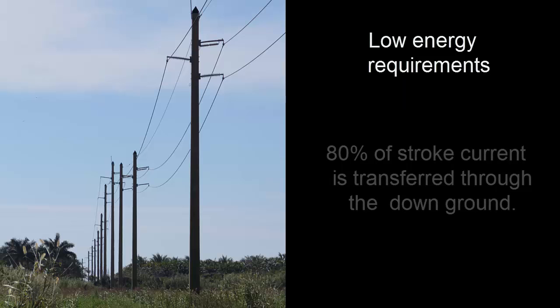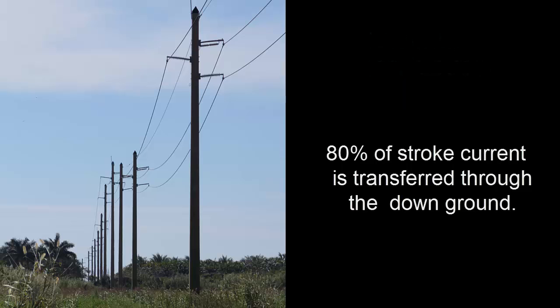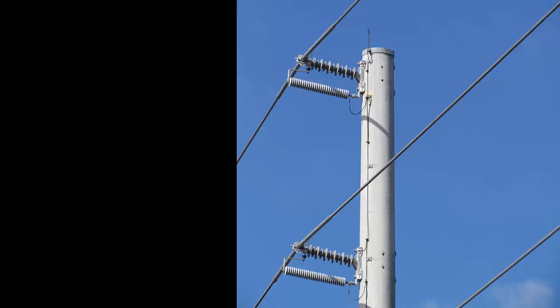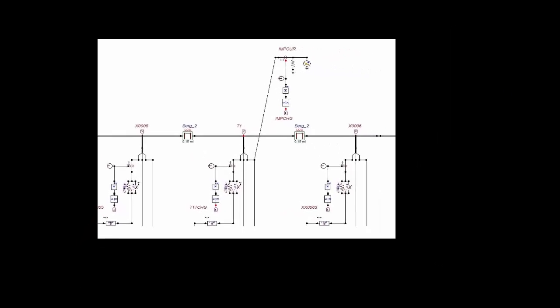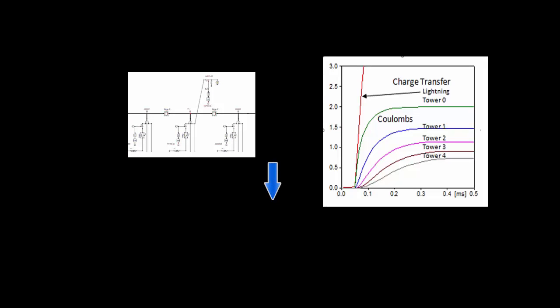This is because 80% of the stroke current is routed to ground via the downground. However, if the arrestors are used on unshielded lines, such as we see in this photo of a 69 kV line in Lakeland, Florida, higher energy may be needed. Theoretically, if there is a 16 coulomb discharge into an unshielded transmission line that has arrestors on each tower, the current and charge is shared very well. In simulations, we find that even with a 16 coulomb stroke, only two coulombs is transferred by the nearest arrestor.